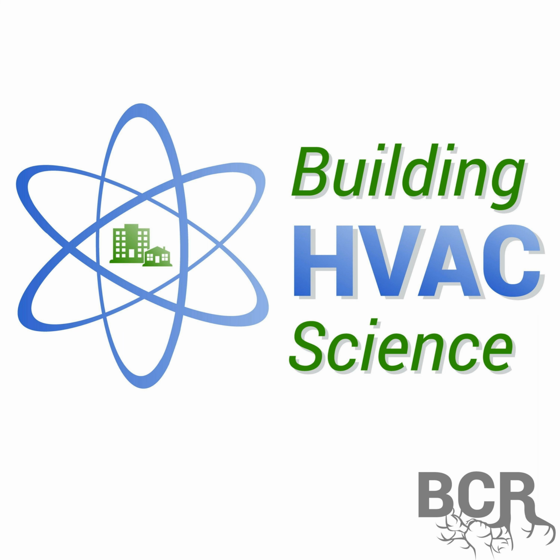The measuring range on this is pretty unlimited, but the resolution and accuracy will be impacted by the exactness of your BTUH measurement and if you correct for air density. It can take up to 20 minutes or more to run this test, and the result you'll get is CFM, cubic feet per minute. Now, this is a good ballpark measurement if done with the proper technique.